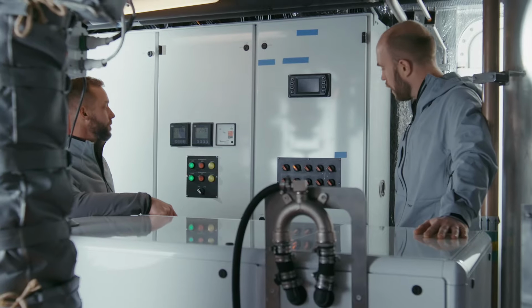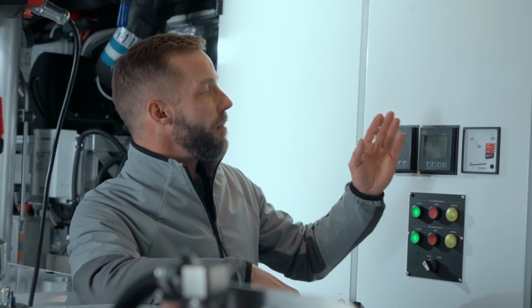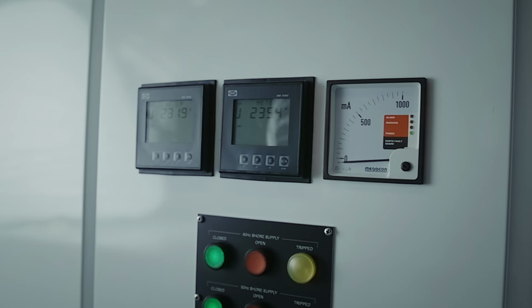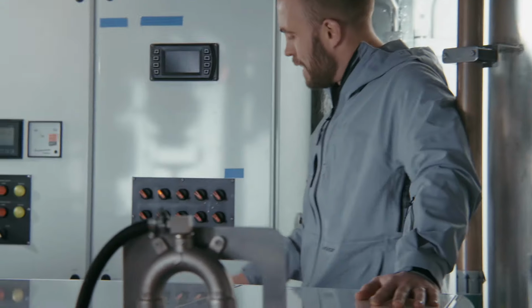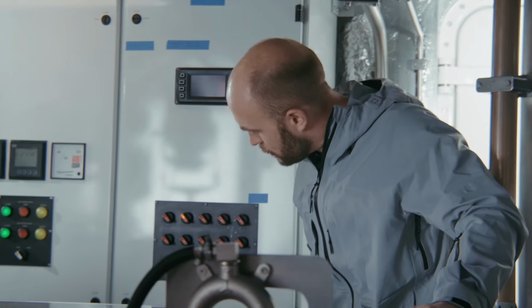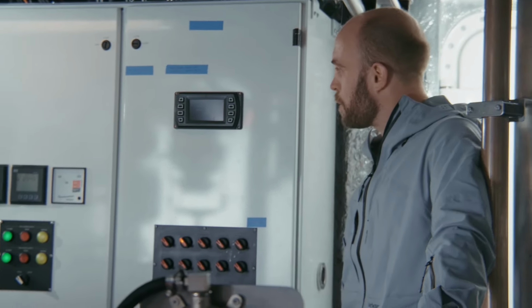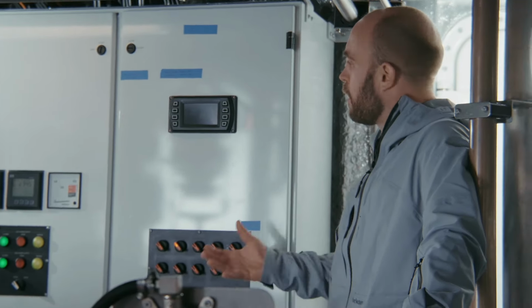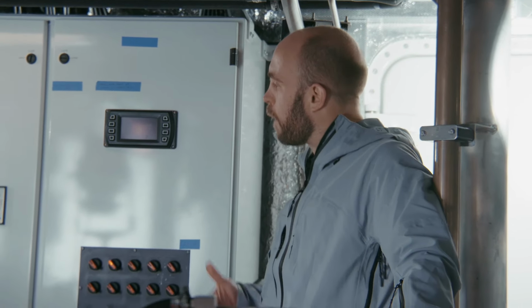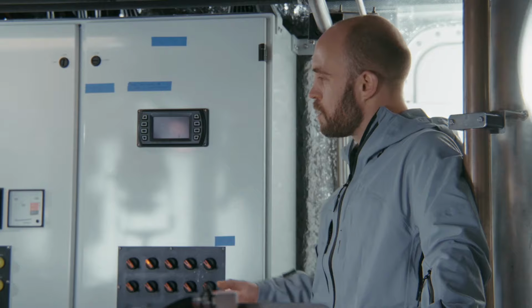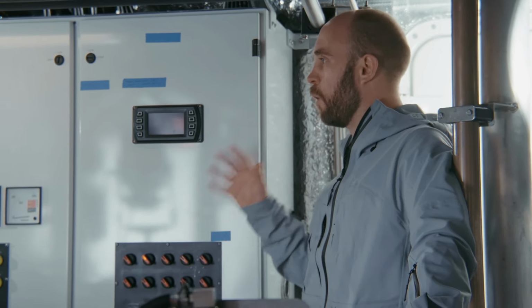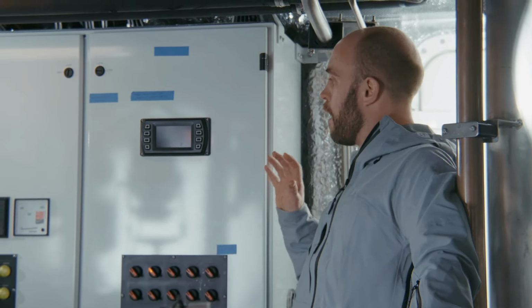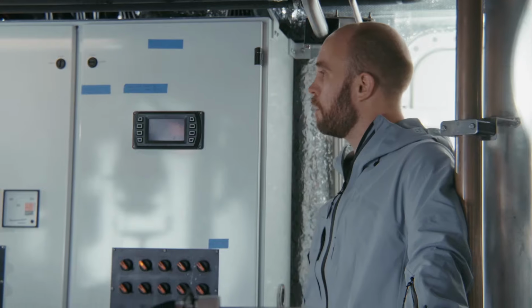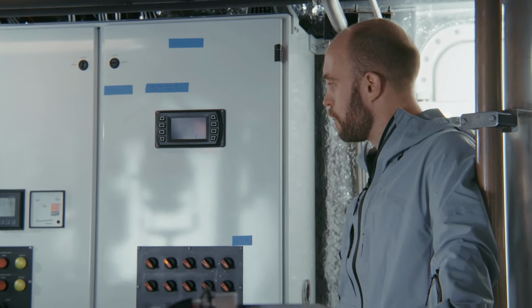Super important. Yeah, absolutely. So moving across a little here, we've got earth fault meters as well, for AC and DC earth fault monitoring. As you'd expect at the moment, neither of those are showing any issues. But say in time there was a connection came loose, something had been worked on, and there was a loose connection or whatever else might be causing an earth fault on either of those systems, you would see that registered here with an alarm on the monitoring system, which allows you to see the extent of the fault, and also helps in the diagnosis and solution of that.